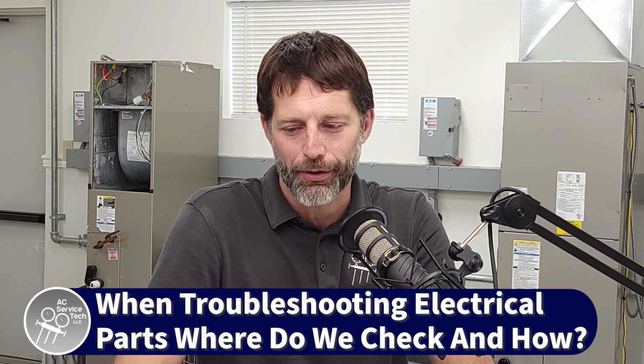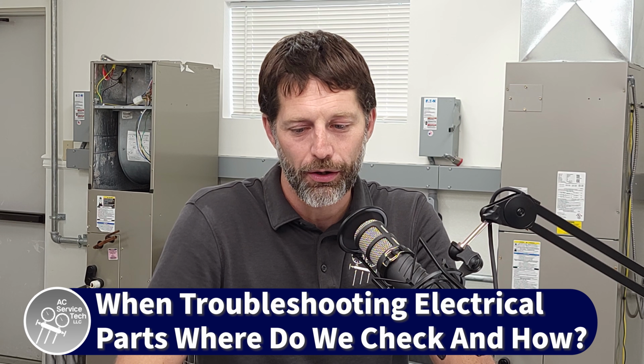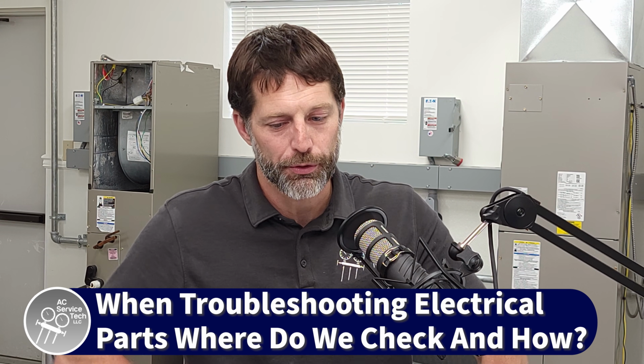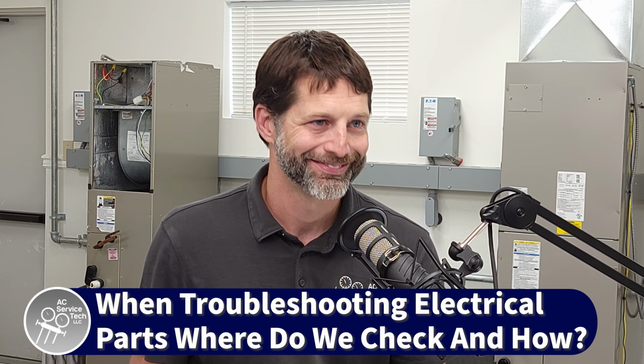A technician named Kevin asks: when troubleshooting electric parts, where do you check and how, on parts like pressure switches, temperature switches, control boards, and electric heaters? Wow, that's a loaded question. First, I would separate it between a switch and a control. If you're looking at a switch, like a pressure switch, you want to see where it opens and where it closes. A high or low pressure switch will have an opening and a closing pressure, or it may just have an opening pressure plus or minus a number.